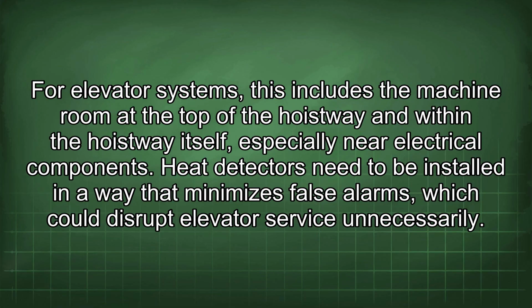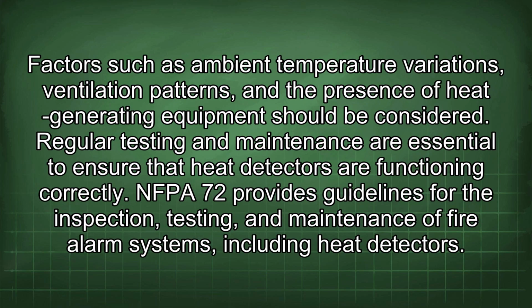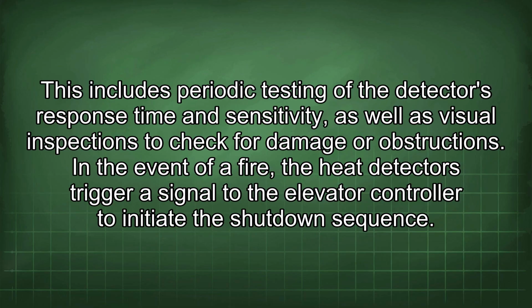near electrical components. Heat detectors need to be installed in a way that minimizes false alarms, which could disrupt elevator service unnecessarily. Factors such as ambient temperature variations, ventilation patterns, and the presence of heat-generating equipment should be considered. Regular testing and maintenance are essential to ensure that heat detectors are functioning correctly. NFPA 72 provides guidelines for the inspection, testing, and maintenance of fire alarm systems, including heat detectors.